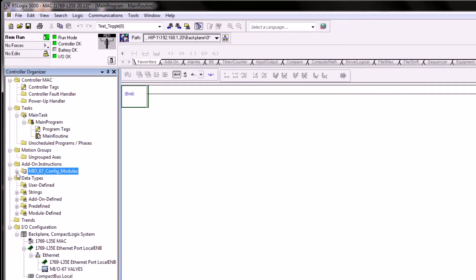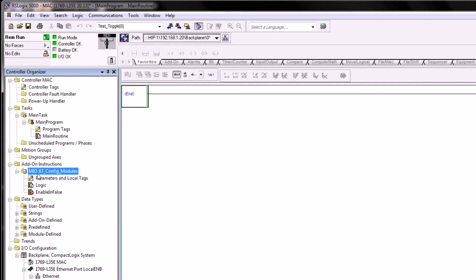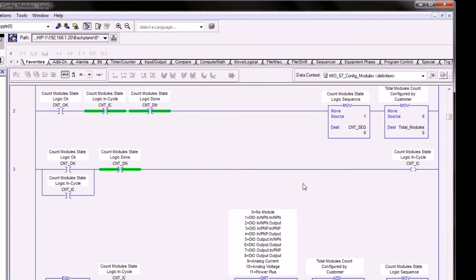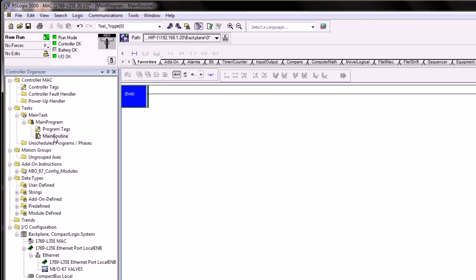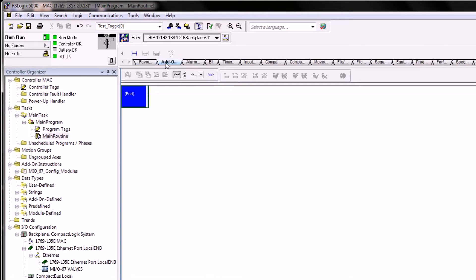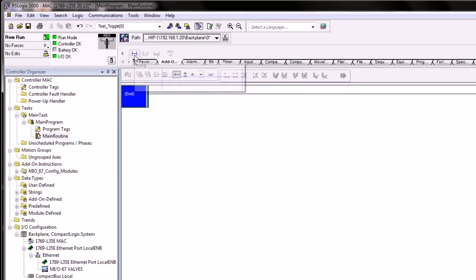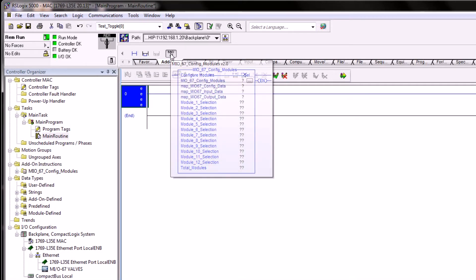Once an AOI is imported, it will appear under the add-on instructions folder, showing the logic and parameter tags associated with it. Normally you don't have to modify anything inside the parameters, local tags, or logic. All MacValves AOIs are unlocked, so you can view the logic inside the block by double-clicking to examine the ladder logic. AOIs appear on the function toolbar at the very top of RSLogix 5000 or Studio 5000. You can click the add-on bar to access imported AOIs, start a new rung, and drag and drop the AOI onto a rung.